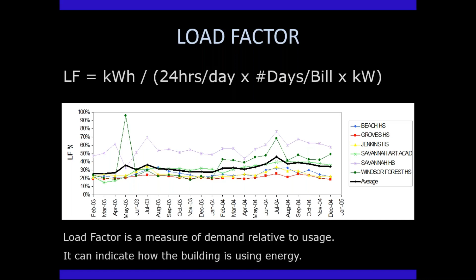Actual kilowatts means metered kilowatts. Average kilowatts is a different concept—you take the total kilowatt hours and divide by the number of hours in the bill, say 25 days times 24 hours, and you end up with the average kilowatts. It's the equivalent of asking: if you just turned something on for the entire billing period, at what demand level would you need to be to get the same kilowatt hours used in the building? That's what average kilowatts represents.